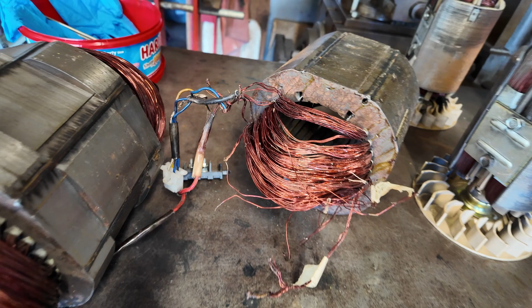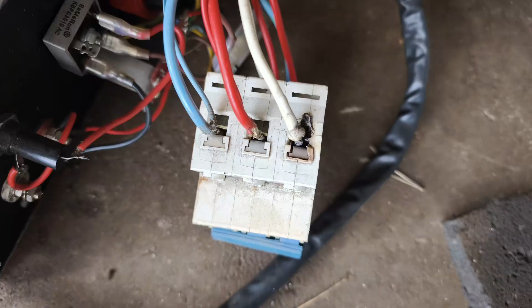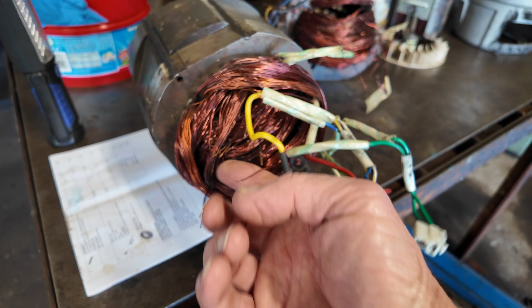This is the one that most recently burnt out, which was my little 3-phase, which I had used for absolutely years. The problem, I think, was caused, it was my fault in a way for not noticing quick enough, that there had a bad connection on the circuit breaker, and that sparked and went ahead, and I suppose that induced enough voltage to burn through the main windings. They shorted out with one of the other coils, again like the exciter or the 12 volt auxiliary coil.